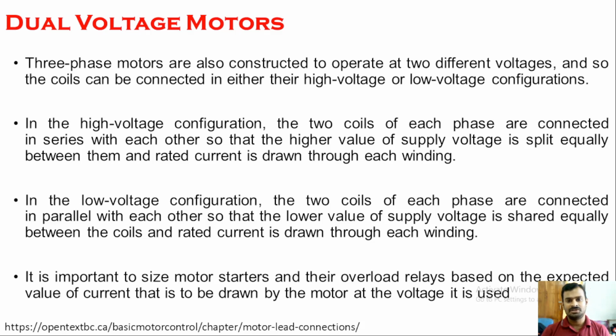In the high voltage configuration, the two coils of each phase are connected in series with each other. So it means in each phase you will have two coils, and if the two coils are connected in series, it will be called the high voltage configuration. And if the same two coils are connected in parallel, it will be called a low voltage, high current configuration. And it is very important to size motor starters and their overload relays based on the expected value of current that is to be drawn by the motor at the voltage it is used.